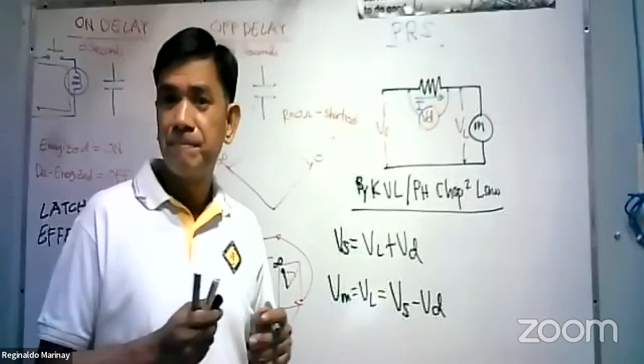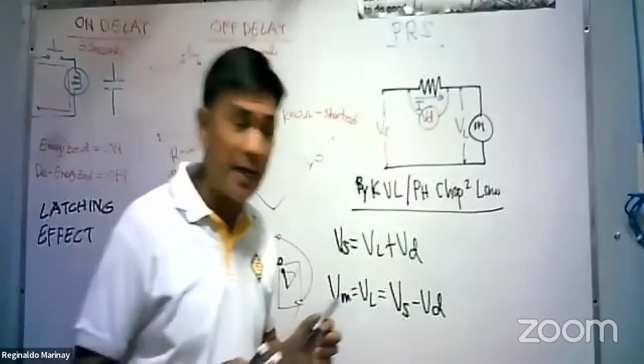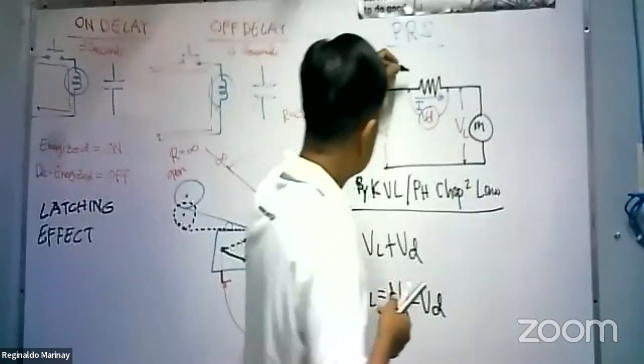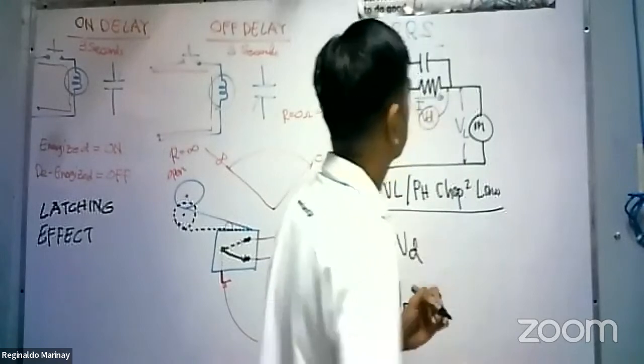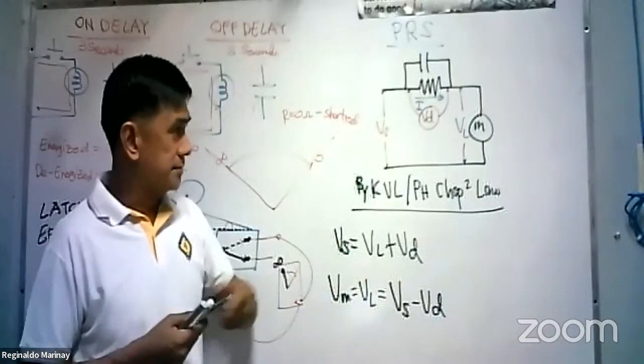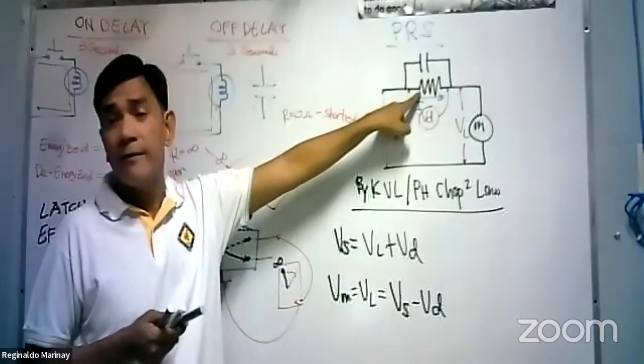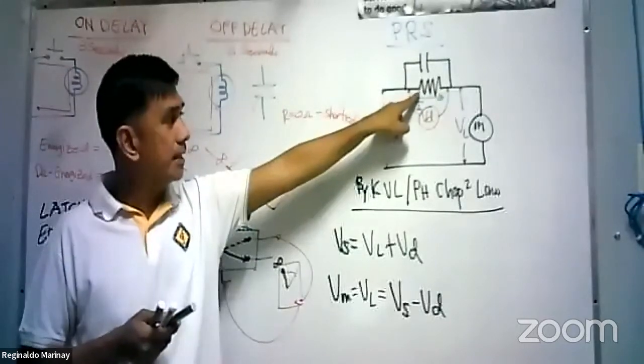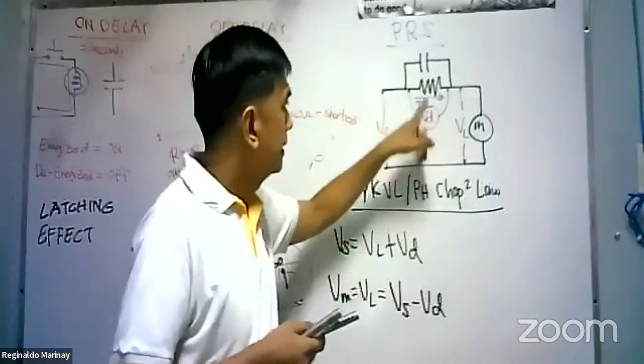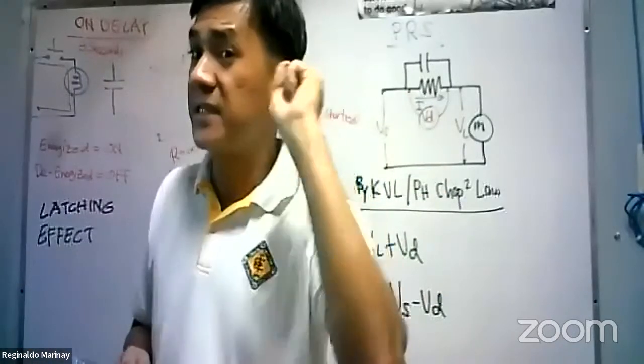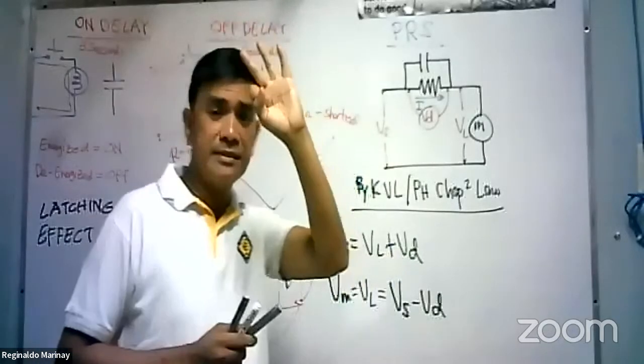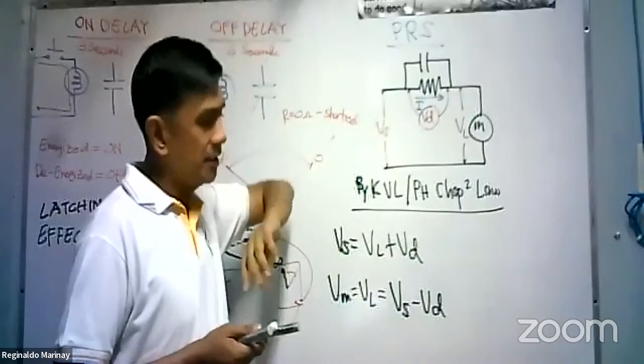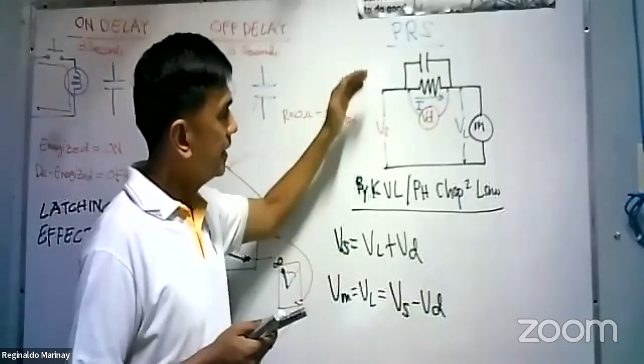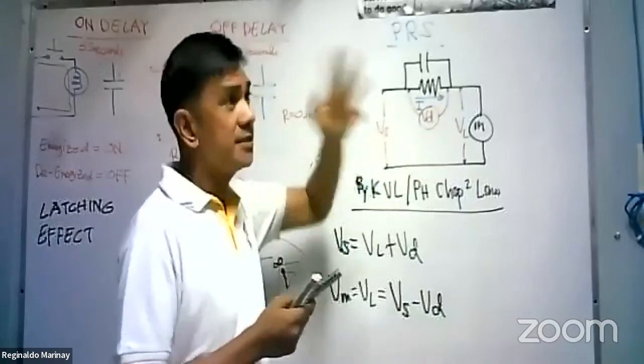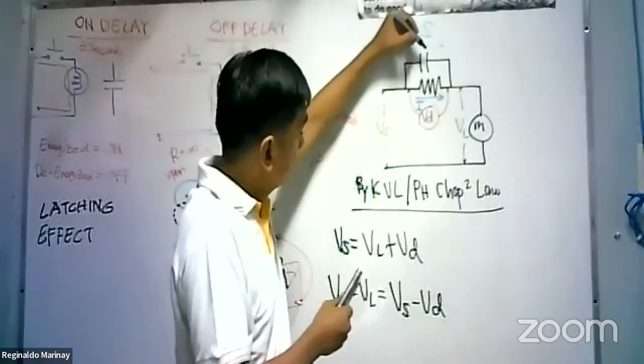Now, what is the application of this resistance? Primary resistance starting. So, we have here a contact. Normally open contact. See? Take a look here. In parallel with the resistor. Let's say you have a timing relay for 3 seconds. On delay timing relay for 3 seconds. Once you switch on, the current will flow here for 3 seconds. Then, once you reach 3 seconds, this will become closed.